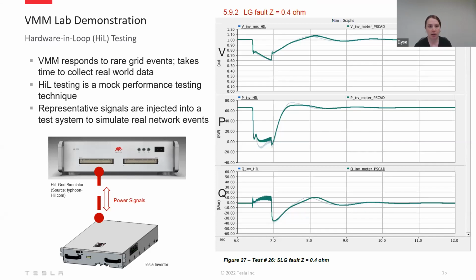So instead we do a kind of lab demonstration testing called hardware in loop, or HIL, testing. This is a mock testing technique where we set up a device that can inject signals into the inverter under test that represent a fault scenario. We tested a lot of different plausible grid disturbances, from frequency disturbances to bus angle shifts and grid fault scenarios. The figure on the right is just an example of one of those results. This is a one phase to ground fault. So imagine something blowing over a transmission line during a storm.